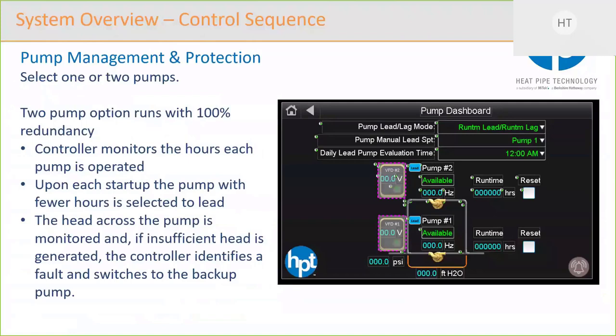So how does it know that a pump has failed? Well, it's measuring the pressure drop across the pump, or rather the pressure increase across the pump, so basically the head being generated. If the pump is being told to operate and it's not generating a head, that creates a fault alarm, and that tells the controller to activate the second pump.